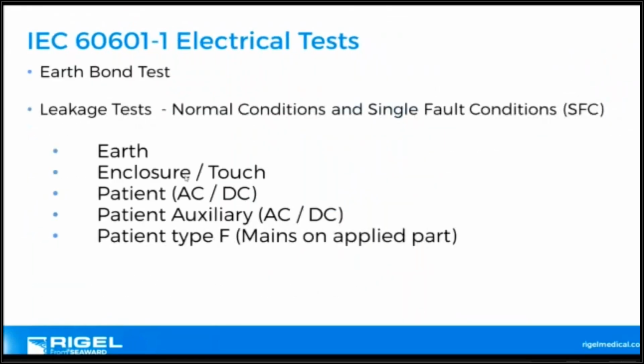What tests do you do with 60601? You do an Earth Bond test, and you do a number of these leakage tests to check for this harmful leakage current that we've determined from previous slides. These are in normal conditions and single fault conditions, and the normal and single fault have various different limits on what is acceptable leakage.